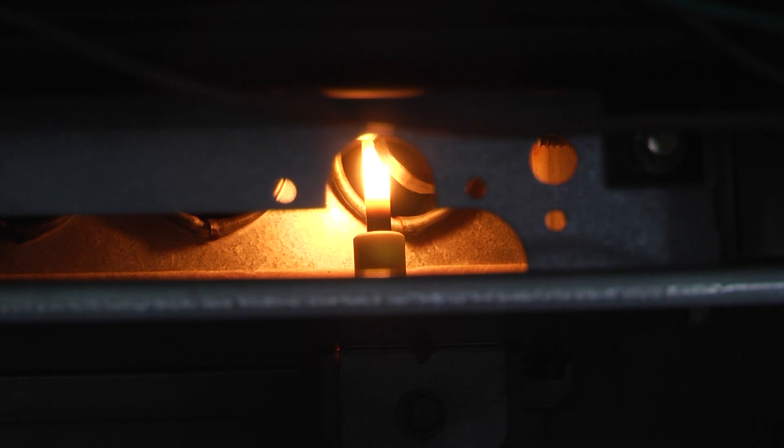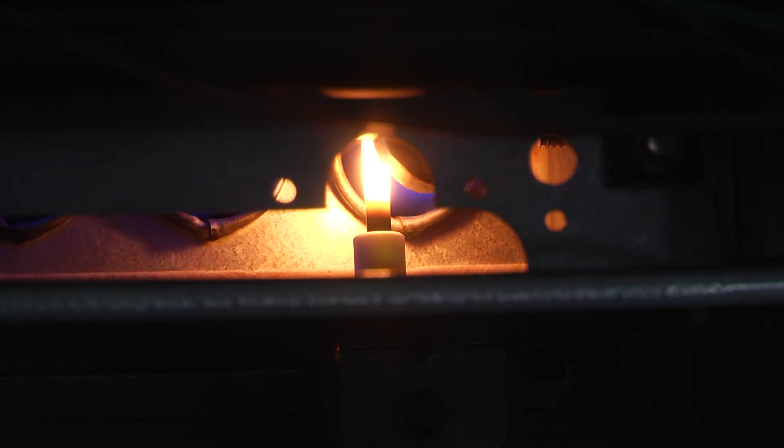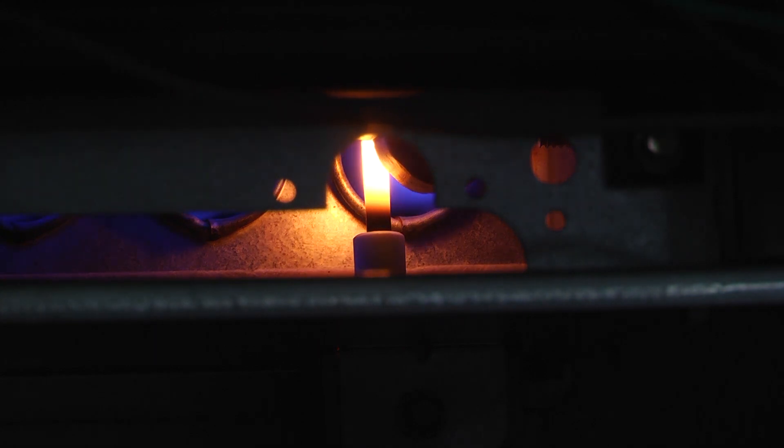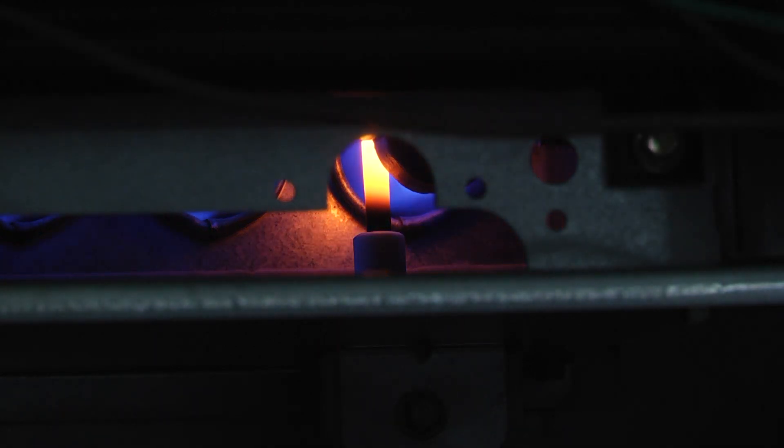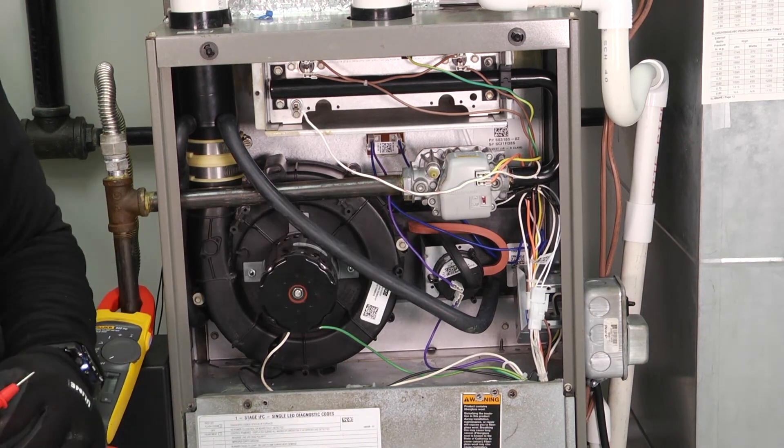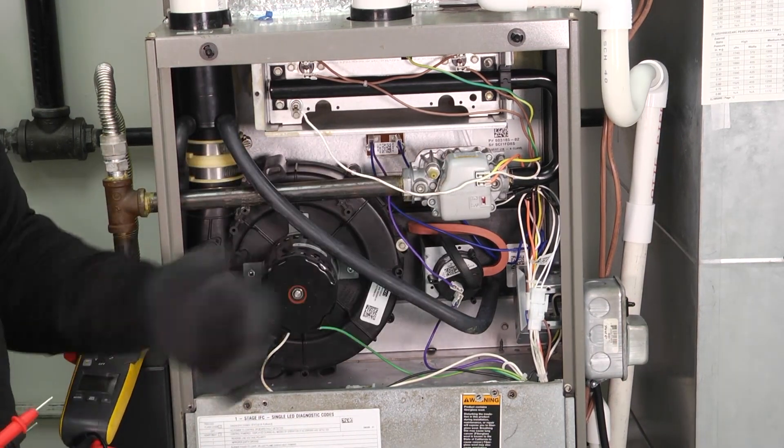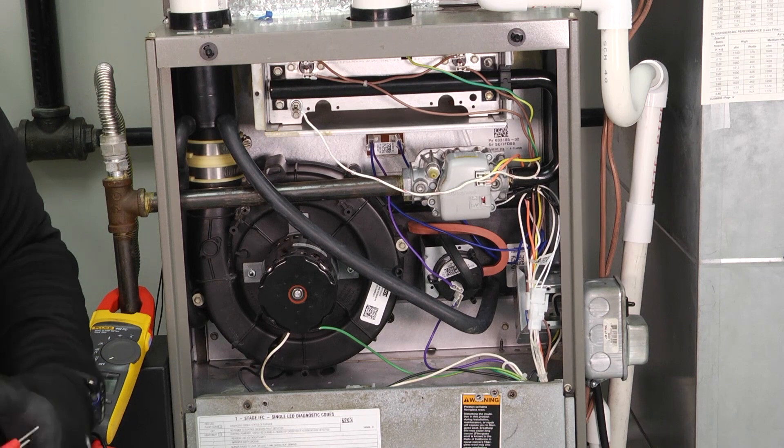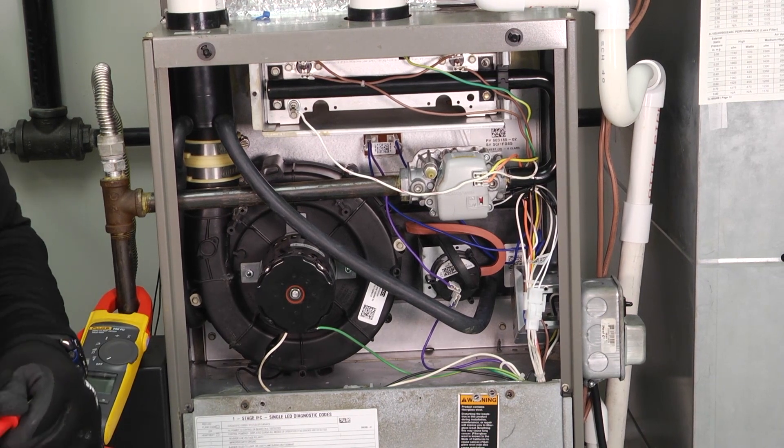And then once the gas valve opens, that helps us ignite our flame there. But sometimes we have to check those and figure out where their resistance is and where the tolerance is so that we can have a conversation to the homeowner about the integrity of their hot surface igniter. It's not a product that we clean or handle. We're just going to take an ohm reading on there and then that ohm reading is going to give us some information about that particular igniter.